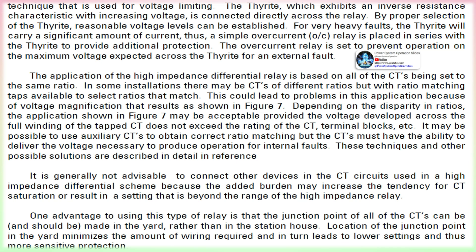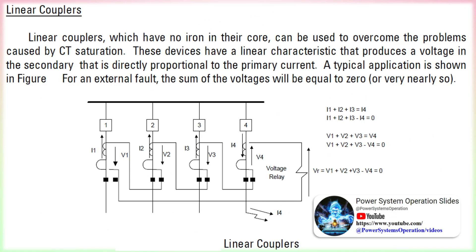The high impedance voltage-operated differential relay is applied on the assumption that the CT associated with the faulted feeder carries the total fault current and saturates completely. For that condition, the CT can be represented by a simple resistive component. The relay, connected across the junction point of the CTs, has an impedance much greater than the total resistance of the CT circuit, comprising CT resistance plus lead resistance. The voltage VR produced across the relay equals the drop in resistance resulting from the total fault current. Calculations are made for each CT circuit to determine the maximum possible voltage assuming total saturation, and the relay is then set greater than this voltage by a suitable margin.